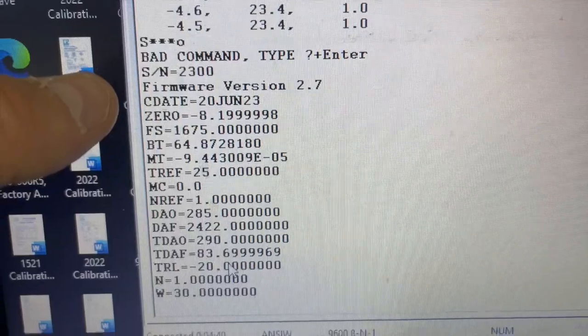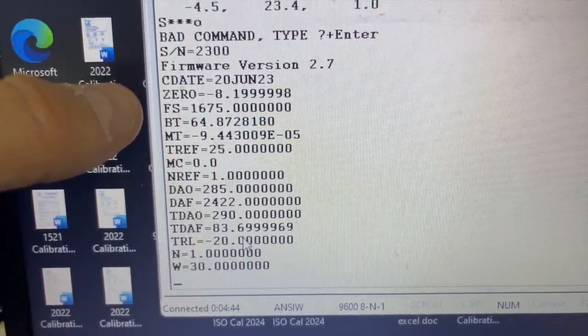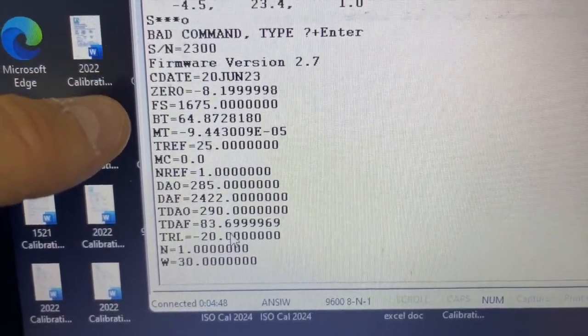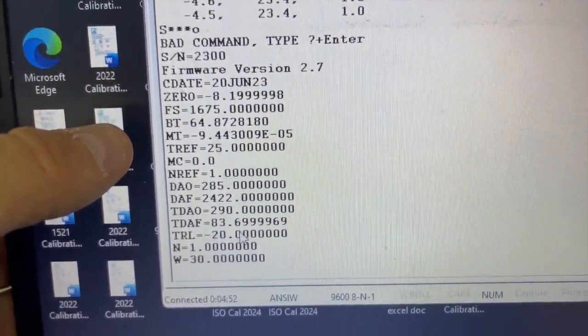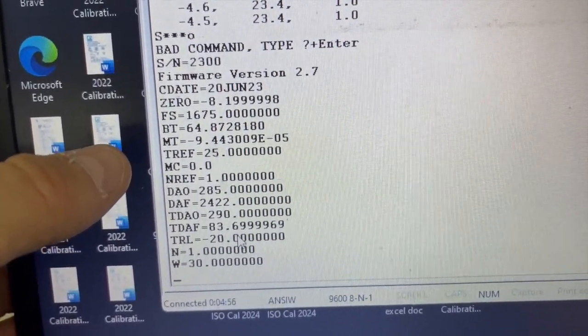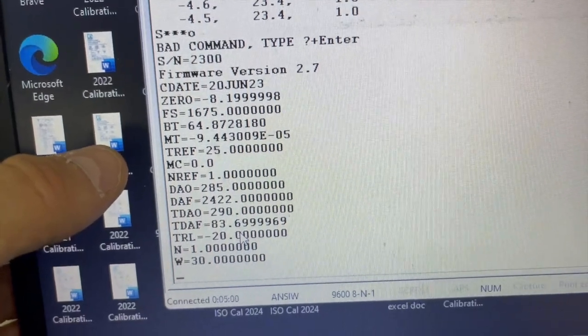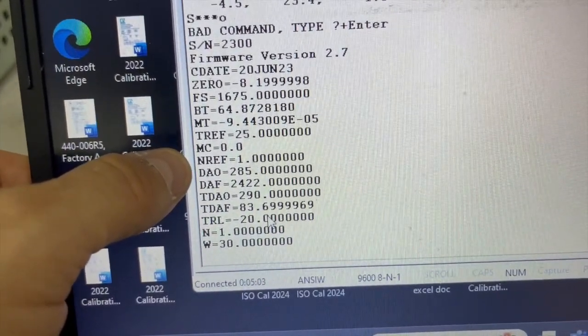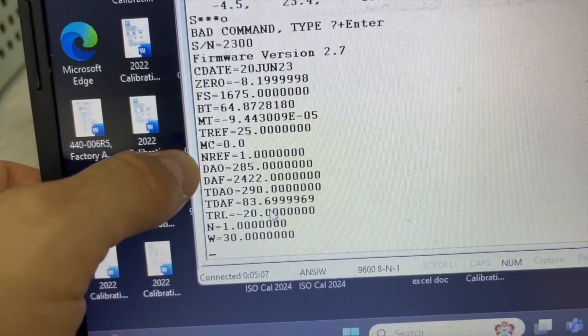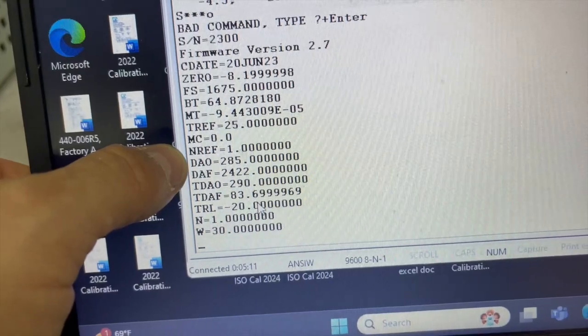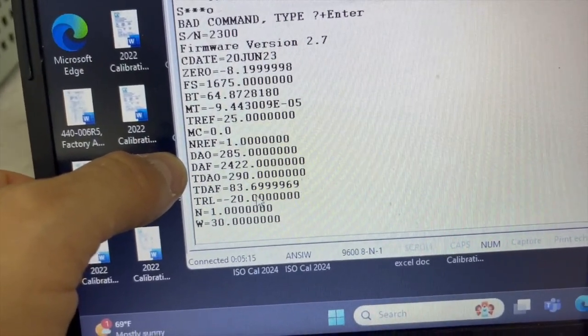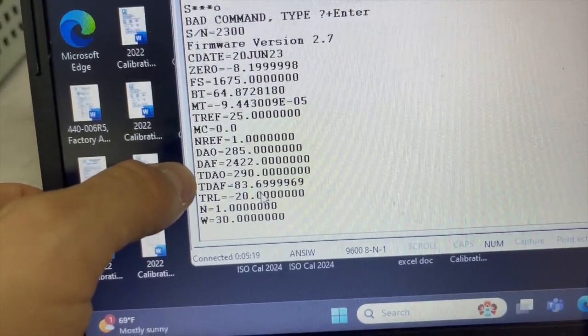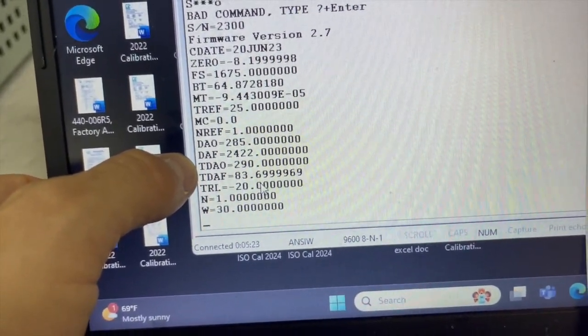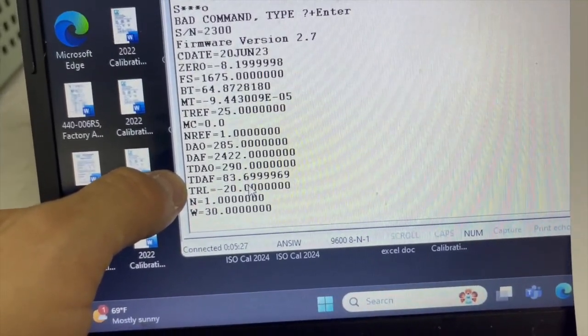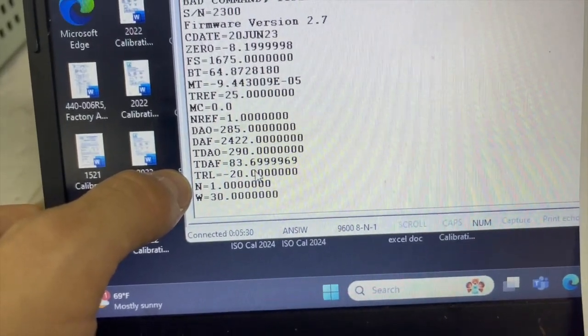You have serial number, firmware revision, calibration date, the conductivity offset, conductivity scale, the temperature offset, temperature scale, compensation temperature reference. You have the compensation factor. You have the reference average. You have DA offset counts, picosiemens per meter. You have the DA slope, picosiemens per meter. You have the DA offset count Celsius. You have the temperature current low end, sample average, weighting factor.